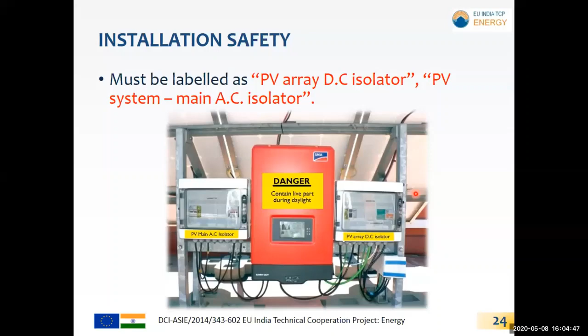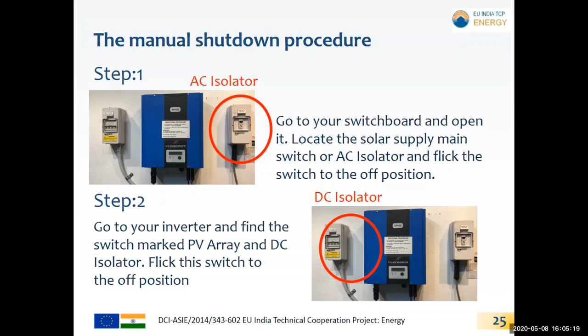Then this is the shutdown process for the O&M. Step 1, switch off the AC isolator, which is next to the inverter or placed in the AC junction box. Step 2, switch off the DC isolator or remove the DC disconnector placed in the DCDB or DC array combiner box. Third step, if your inverter has a DC disconnector or DC isolator switch, flick this switch to the off position. If you do not have one, skip this step.